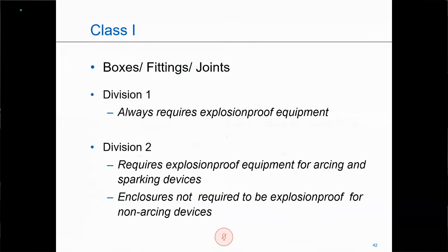Now, when I'm in an area that is Class 1, Division 1, and I'm using the explosion-proof protection technique, my boxes and fittings are required to be explosion-proof. When I'm in Class 1, Division 2, anytime I have an item that is an arcing source, a motor starter, circuit breaker, relays, that equipment is also going to be explosion-proof. But if I have items that are non-arcing, such as a splice box, a terminal housing, those particular enclosures and fittings are not required to be explosion-proof.